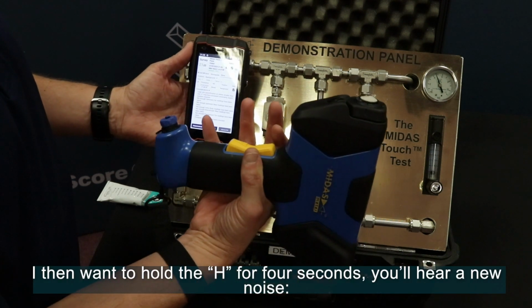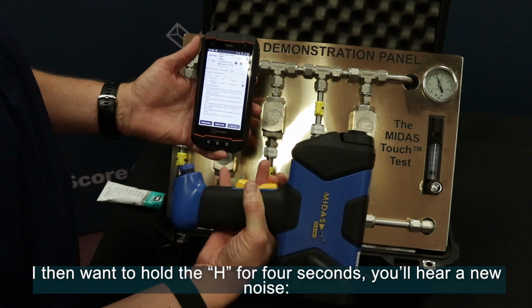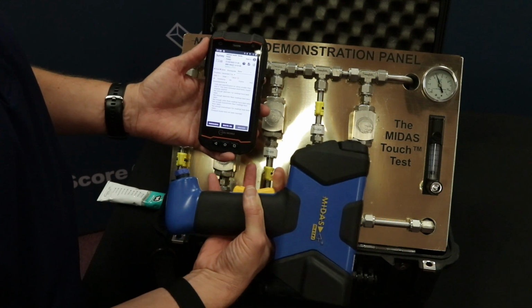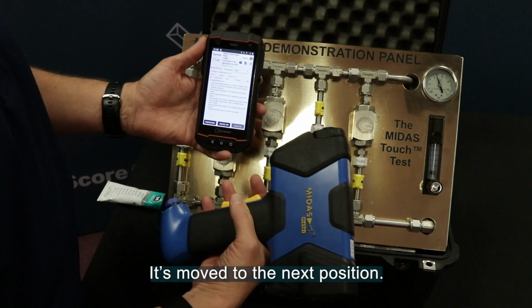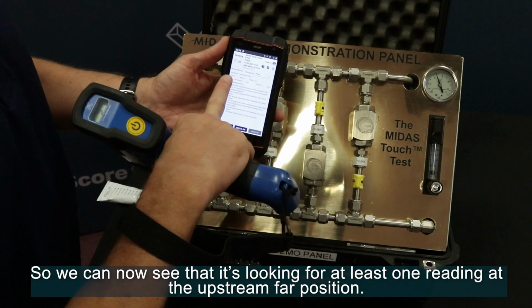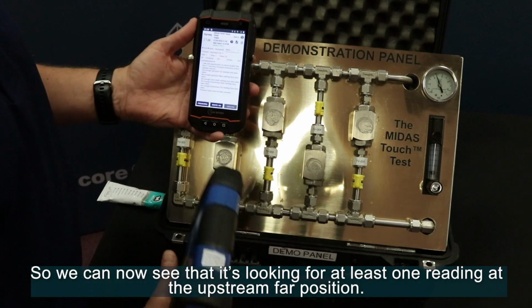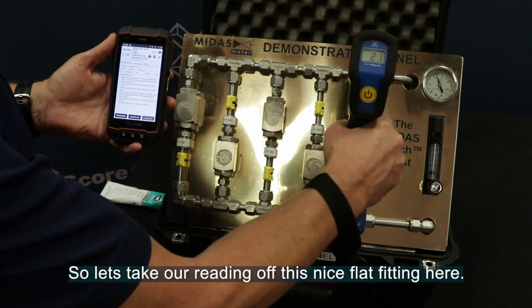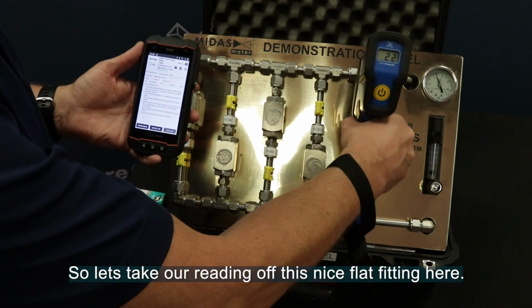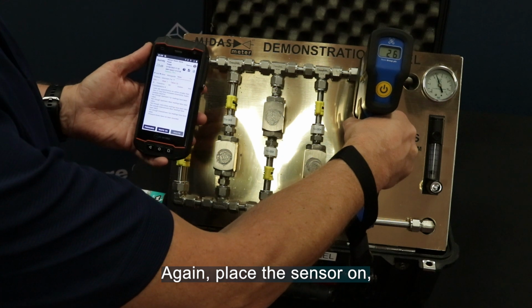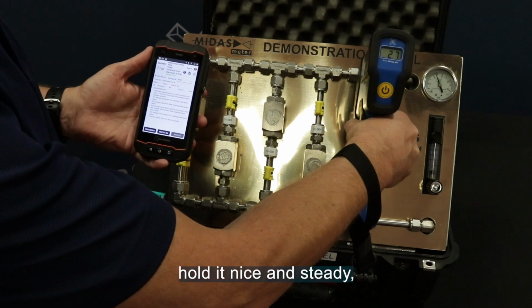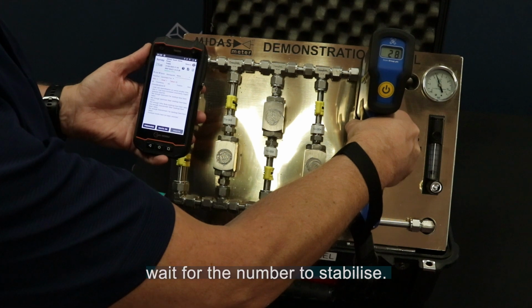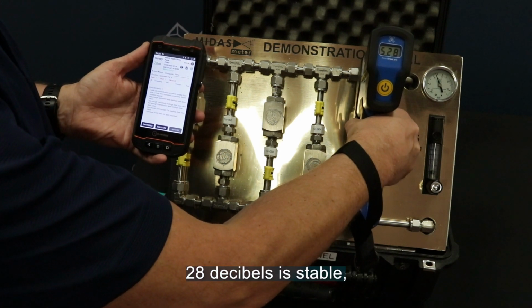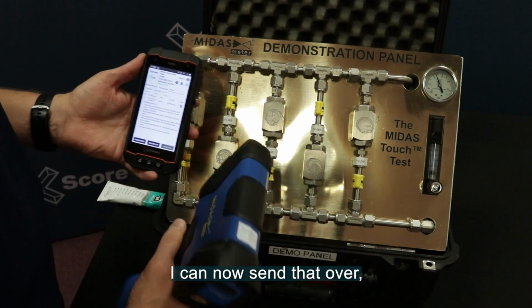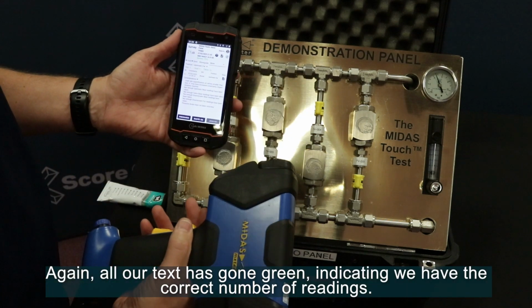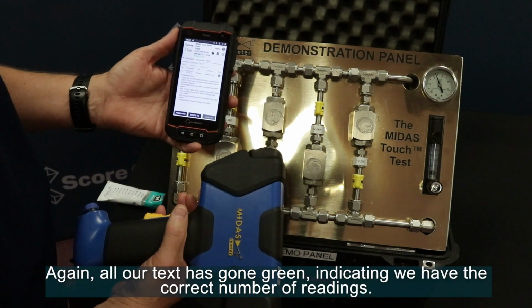I then want to hold the H button for 4 seconds. You'll hear a new noise. It's moved to the next position. So we can now see that it's looking for at least one reading at the upstream far position. So let's take our reading off this nice flat fitting here. Again, place the sensor on, hold it nice and steady, wait for the number to stabilize. 28 decibels is stable. I can now send that over. Again, all our text has gone green, indicating we have the correct number of readings.